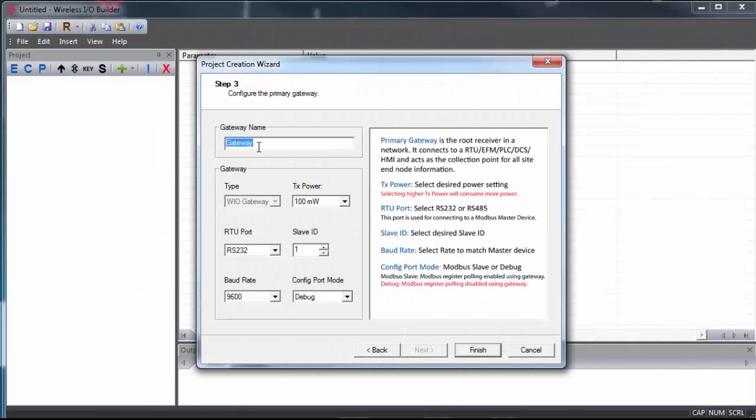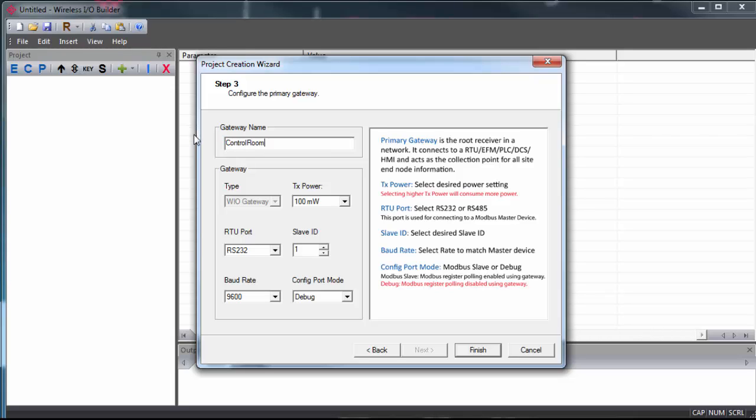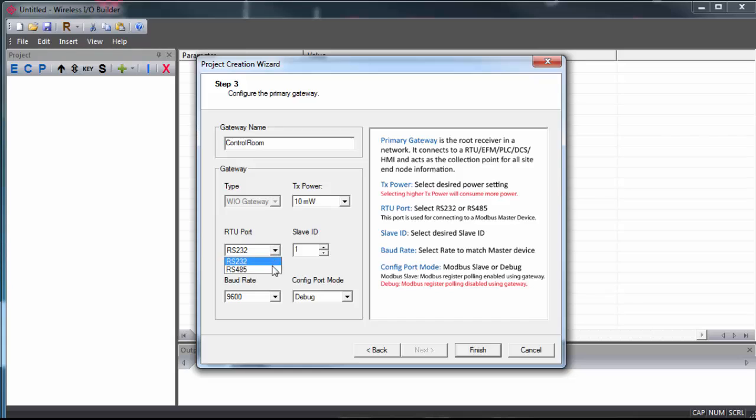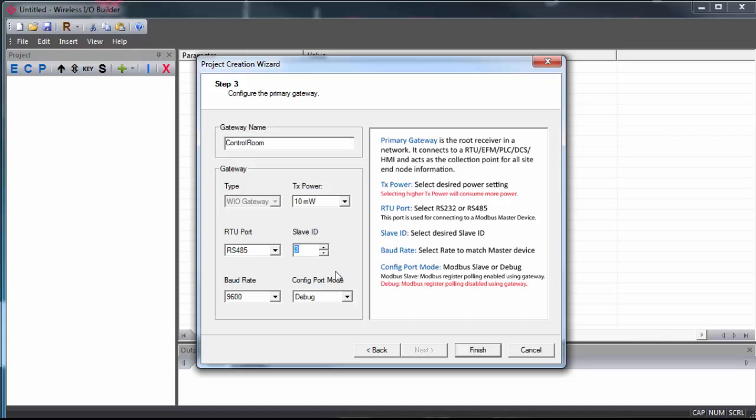Next, we'll configure the primary wireless gateway. We'll give the gateway a name. This is what we'll see in the project. We can select the power output to the antenna. Be sure to select 10 mW or higher for any sort of real application. And we have our Modbus RTU setting. The slave ID is what the gateway will be assigned on your Modbus network. You would set the baud rate to match what you're using on your network as well.